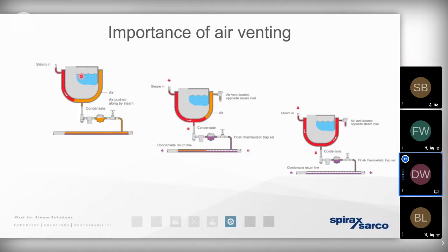So the condensate is going to fall under gravity as a heavier liquid. So it makes sense to fit the steam trap at the bottom of the heat exchanger. So once the system has been operational for a few minutes, for a short period of time, the steam is going to pass, it's going to push a bubble of air past the condensate takeoff. So at that point, without any air vent being present, we would have a bubble of air, an insulating film of air, being airlocked within the heat exchanger itself. So that means there'd be a huge area of space that the steam simply couldn't occupy. So we'd be exposed to an uneven transfer of energy from the steam into the process, and ultimately a slowdown in the process. The process time would extend and extend.